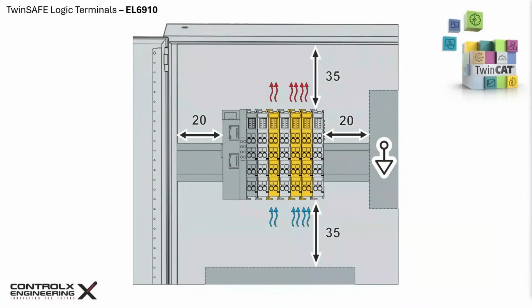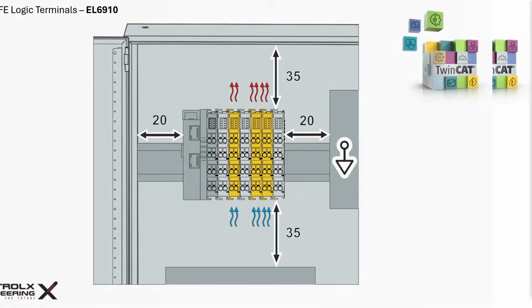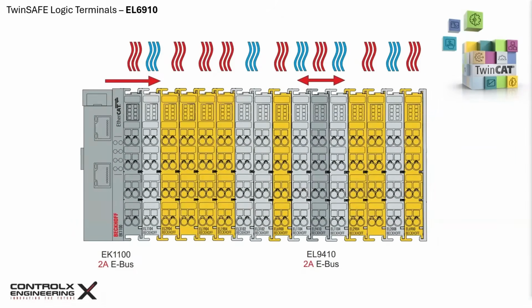During panel layout design, maintain minimum distances. Shown here are the recommended minimum safe distances between neighboring devices and the control cabinet walls. This ensures optimum convection cooling. If optimal spacing is not observed, the TwinSAFE components may overheat and could trigger shutdown of the affected components. The TwinSAFE components have a higher thermal waste compared to the regular non-TwinSAFE terminals, and it's a good idea to mix the terminals to prevent localized hotspots.